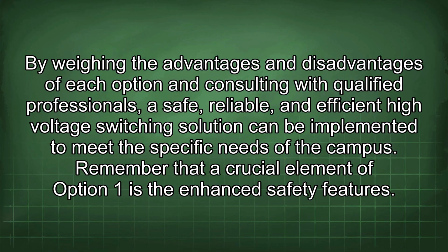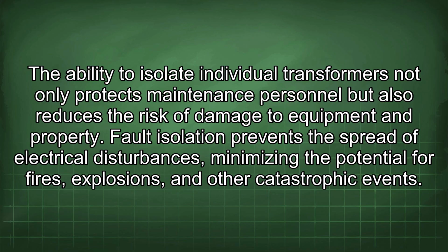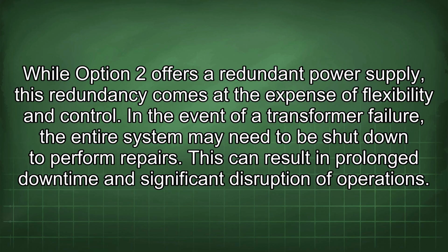Remember that a crucial element of option 1 is the enhanced safety features. The ability to isolate individual transformers not only protects maintenance personnel, but also reduces the risk of damage to equipment and property. Fault isolation prevents the spread of electrical disturbances, minimizing the potential for fires, explosions, and other catastrophic events. While option 2 offers a redundant power supply, this redundancy comes at the expense of flexibility and control. In the event of a transformer failure, the entire system may need to be shut down to perform repairs. This can result in prolonged downtime and significant disruption of operations.